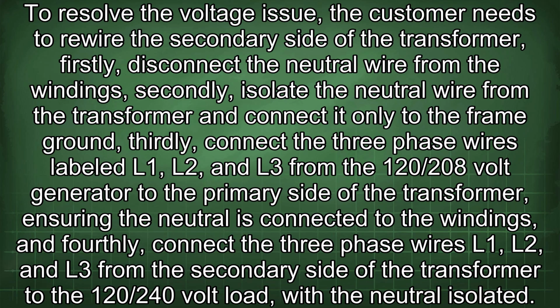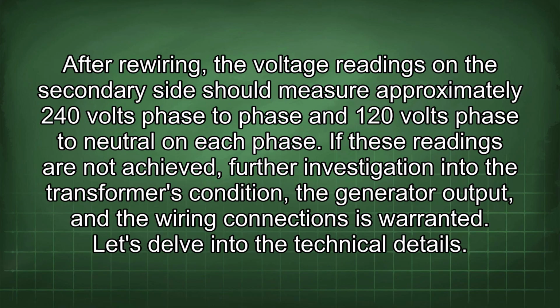And fourthly, connect the three-phase wires L1, L2, and L3 from the secondary side of the transformer to the 120/240 volt load, with the neutral isolated. After rewiring, the voltage readings on the secondary side should measure approximately 240 volts phase to phase and 120 volts phase to neutral on each phase. If these readings are not achieved, further investigation into the transformer's condition, the generator output, and the wiring connections is warranted. Let's delve into the technical details.